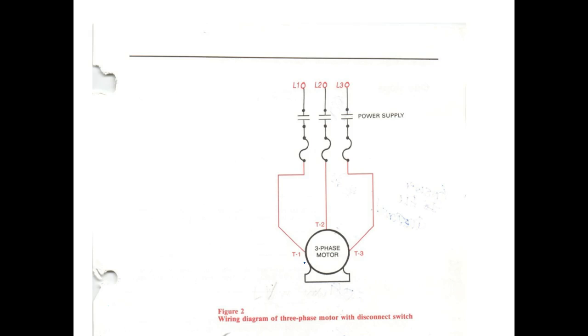So what would happen if I had a 3-phase motor and one of these lines opened up while the motor was running? We refer to this as single phasing. It's a 5 horsepower motor, guys, that sucker is going to try to develop 5 horsepower. So what's going to happen is the other 2 phases are going to pull a lot of current, and the motor's going to hum at you a lot. So we'll try to get a clamp on that meter when y'all do this, since we're going to deliberately single phase this.